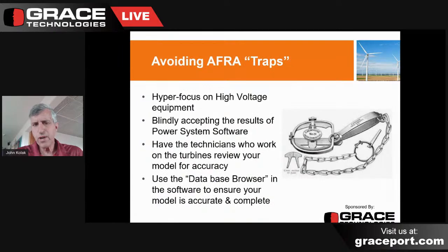So to avoid some basic traps, one thing I recommend is don't hyper-focus on the high voltage equipment. Although, realizing from a work practice standpoint, any work done on high voltage windings, and in this case we're talking about your 12 kV and above, normally that's all done with insulated sticks. You're rarely ever doing that right in the gear itself. So from an arc flash standpoint, your low voltage systems often are more dangerous than the high voltage, simply because normal work practices would have you some distance away on high voltage systems.